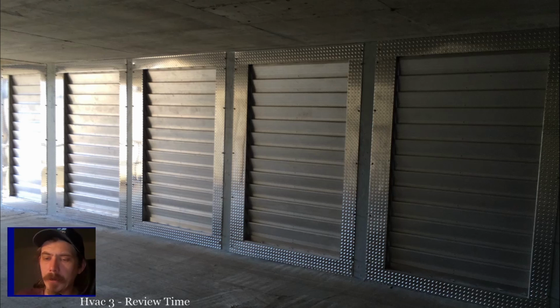Oftentimes, a rooftop unit is not a great location for a drive. Even if it's in the airstream, when that unit is in an unoccupied state and not moving air, you could still end up putting the VFD in an environment that is not suitable for the drive. So pay close attention, especially if you're having drive failures or something like that. Pay very close attention to the environment the drive is in.